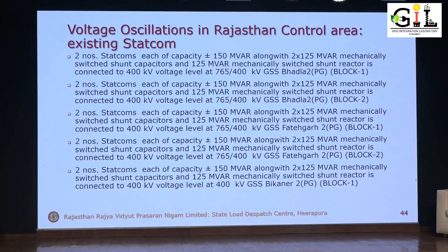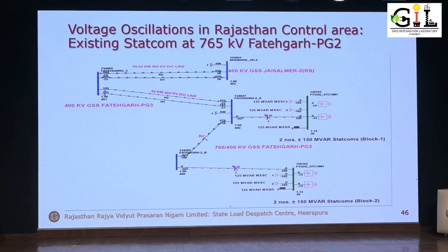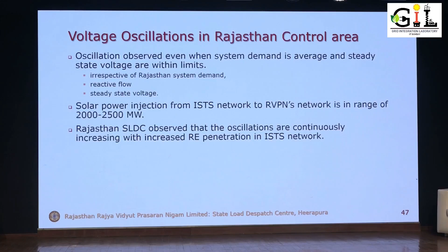Another set of STATCOMs at Fatehgarh are connected to RVPN's Jaisalmer 2 substation. We found that irrespective of Rajasthan's demand being low, with reactive power within Rajasthan not changing and voltages steady state, suddenly solar injection in the ISTS network changed, and Rajasthan observed these oscillations. We are continuously in touch with the RLDC, and they are doing a detailed study in this regard.